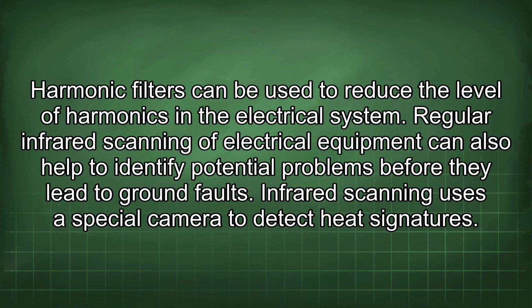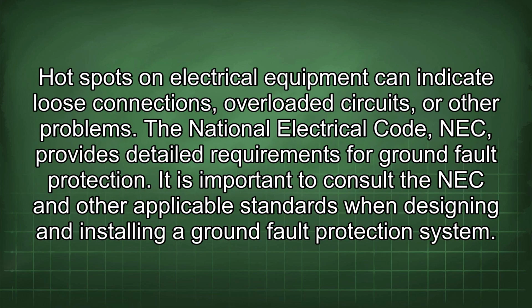Regular infrared scanning of electrical equipment can also help to identify potential problems before they lead to ground faults. Infrared scanning uses a special camera to detect heat signatures. Hot spots on electrical equipment can indicate loose connections, overloaded circuits, or other problems.